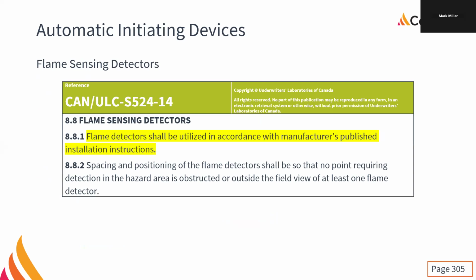So the flame detectors are really, really interesting, but incredibly rare because there are some pretty significant limitations with where you can install them and what they're susceptible to, and then the sheer cost. These things are very, very expensive. And so we use them very sparingly. The other issue being, of course, they are line of sight, so we have to make sure that we put enough in so that we don't have any obstructed views. We need to have some pretty decent overlap so that every single spot in the entire area to be protected is visible from at least one flame detector.